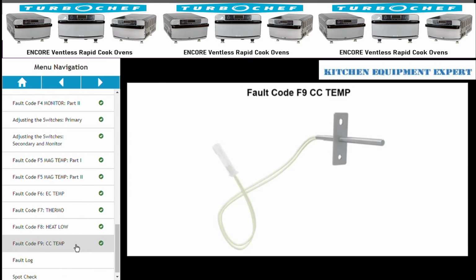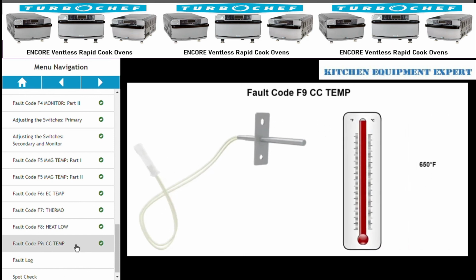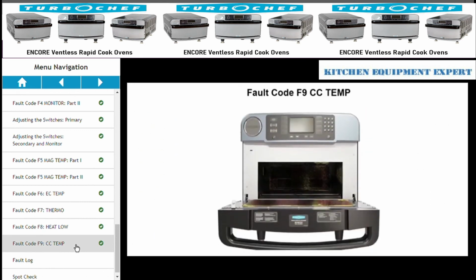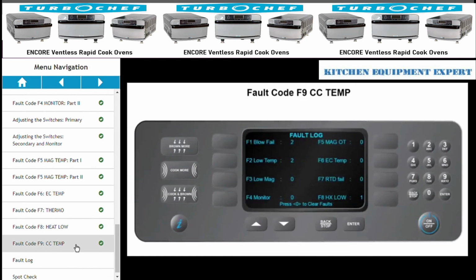Fault code F9 will be triggered when the RTD senses a temperature of 650 degrees Fahrenheit, or 343 degrees Celsius, in the oven for a period greater than 40 seconds, but less than 2 minutes. One cause could be a buildup of grease or other combustibles that has caused the catalytic converter to flash. This fault will only appear in the fault log and will not be displayed.